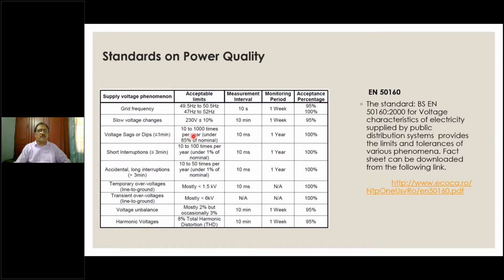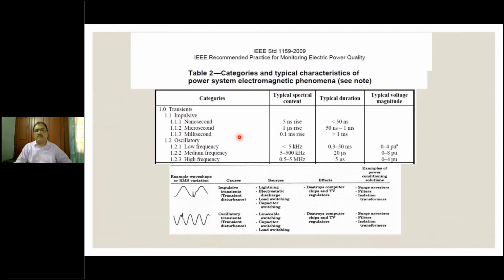This particular information on voltage sags and dips is a half cycle value. 10 milliseconds is half a cycle, 20 milliseconds is 1 cycle, so in 50 hertz there are 50 cycles in one second. If you capture the value for 1 year, 100% of the time the sag should be within this limit: 10 to 100, 1000 times, under 85% nominal. It should meet this, because sag causes a lot of damage to production efficiency, and a lot of interruptions are caused by sag. Again, I'm repeating, voltage sags and dips are very important for us to understand.